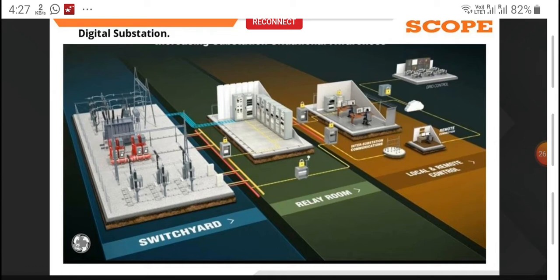The output of the CT or PT is mostly sampled values, which are digital values, and there is a merging unit which conditions those signals and sends them on the protocol called 61850 9-2, or 9-LE, the light edition. The 9-2 is mostly sampled value signals carried from CT or PT to the relays. So the copper is completely eliminated, and in its place you lay a single optical fiber, so that all the signals are shared through that optical fiber to the different relays.